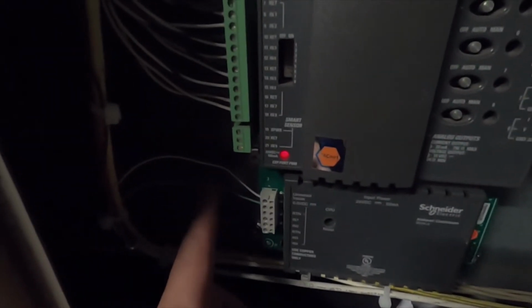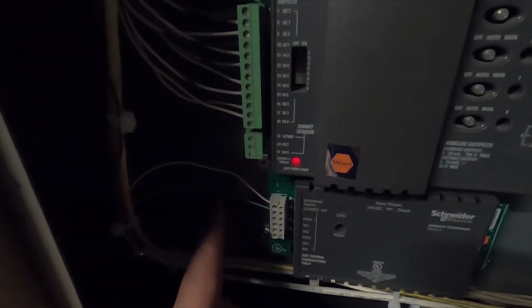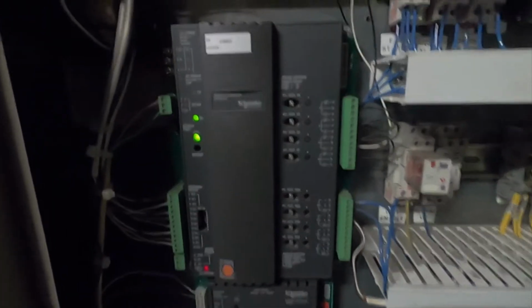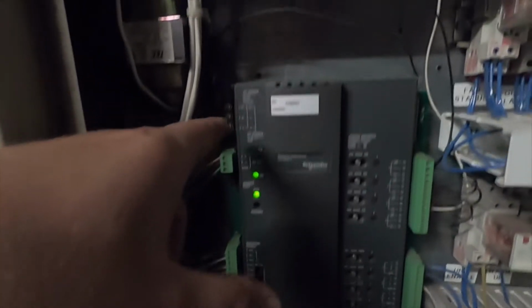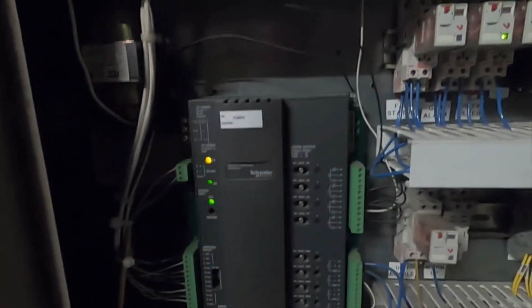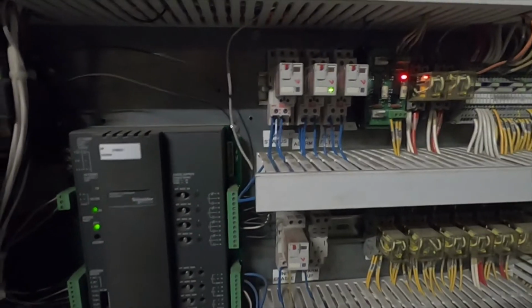So you have these 2 conductors right here. One is from your humidity, one is from the CO2, and it's using a 0 to 5 volt signal, and then we draw 24 volts off here to power both in series. Relays for controls as well.